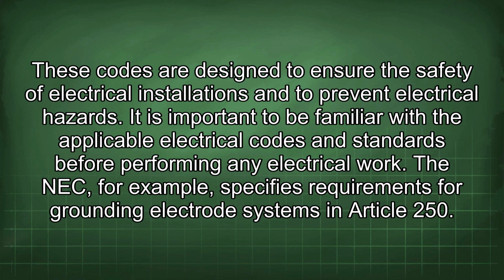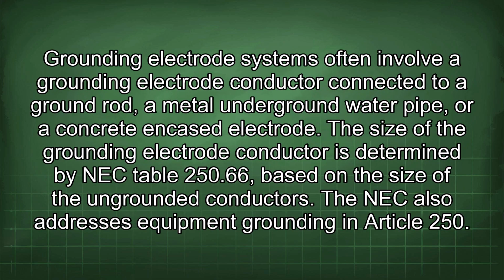The NEC, for example, specifies requirements for grounding electrode systems in Article 250. Grounding electrode systems often involve a grounding electrode conductor connected to a ground rod, a metal underground water pipe, or a concrete encased electrode. The size of the grounding electrode conductor is determined by NEC Table 250.66 based on the size of the ungrounded conductors.